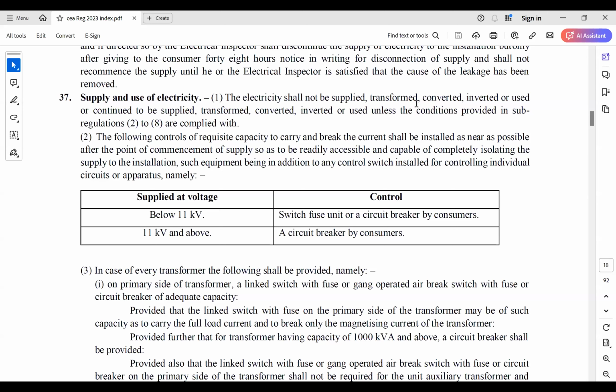I do completely agree with the safety aspect of things, but only for the safety aspect. Like I mentioned, in a clear case, after the point of supply the consumer had provided a switch fuse unit, and there was a transformer 100 meters away at the rear end of the factory. There, a circuit breaker was provided on the upstream and downstream. Still, the electrical inspector insisted on providing another circuit breaker to the consumer after the point of supply, and his transformer was hardly 400 kVA, 500 kVA.